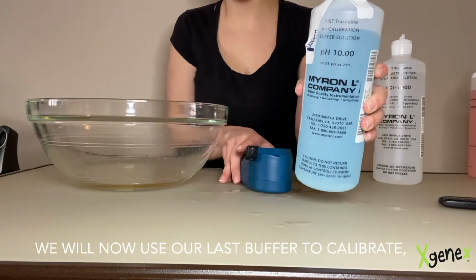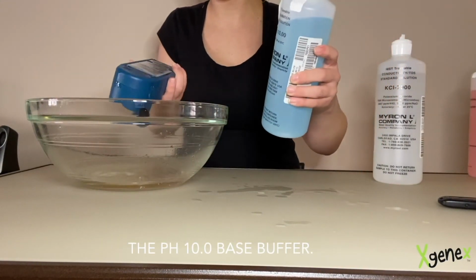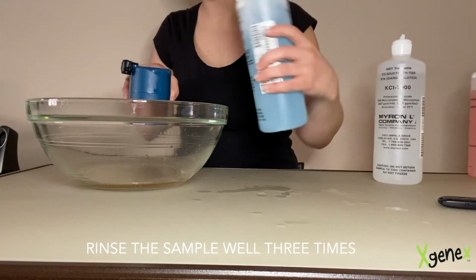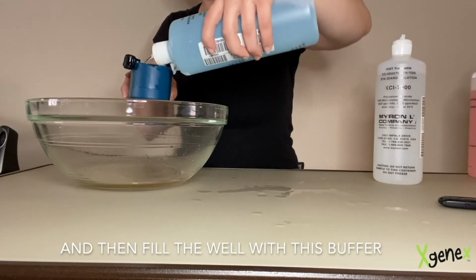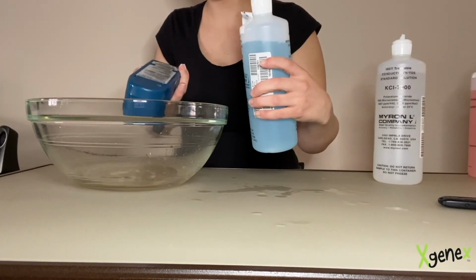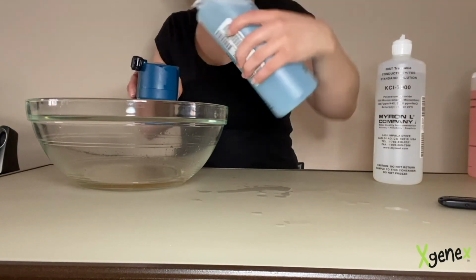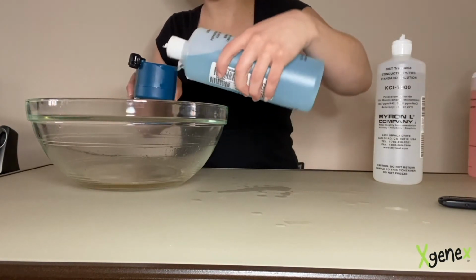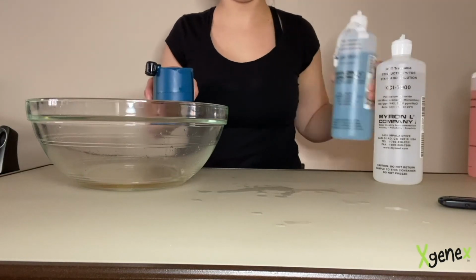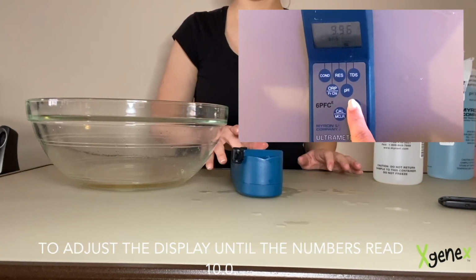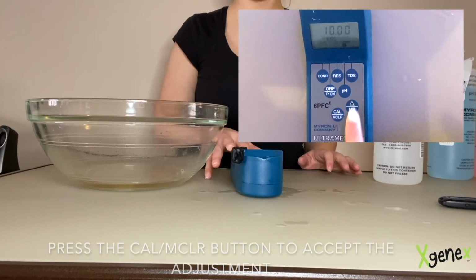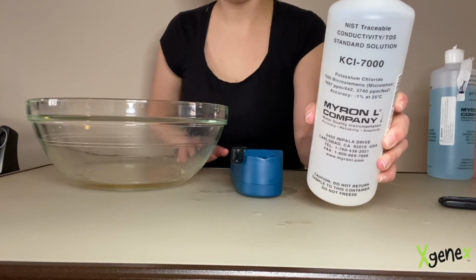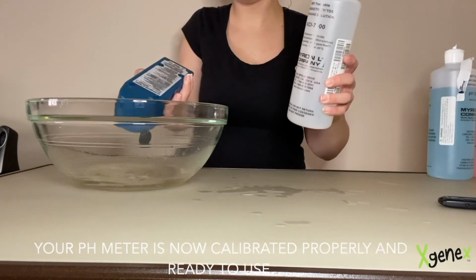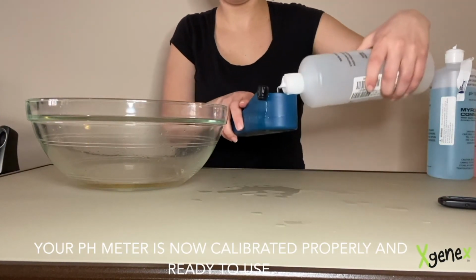We will now use our last buffer to calibrate, the pH 10.0 base buffer. Rinse the sample well 3 times and then fill the well with this buffer. Use the up-down arrows if necessary to adjust the display until the numbers read 10.0. Press the Cal button to accept the adjustment. Your pH meter is now calibrated properly and ready to use.